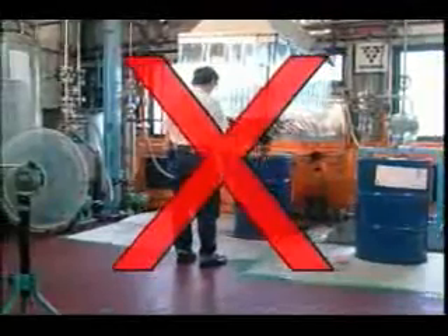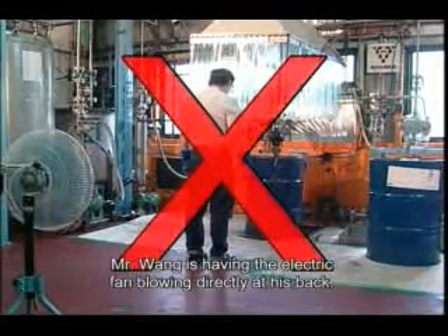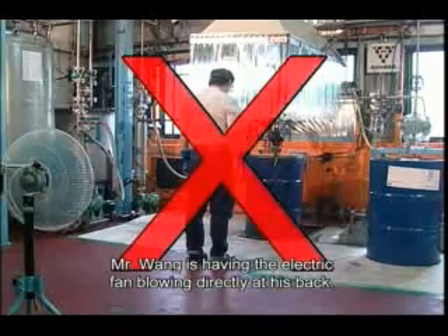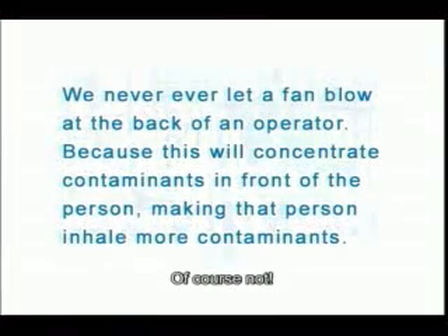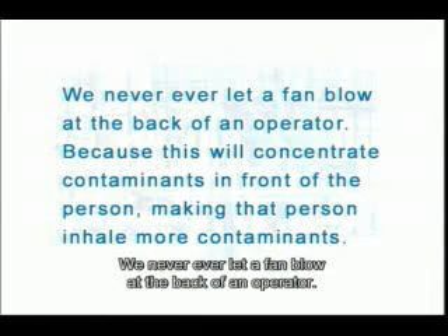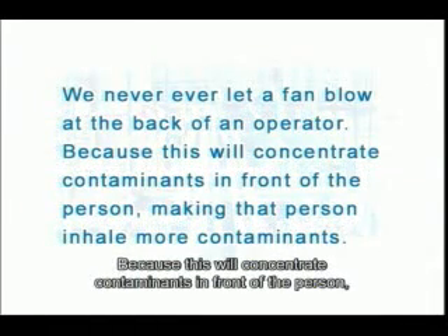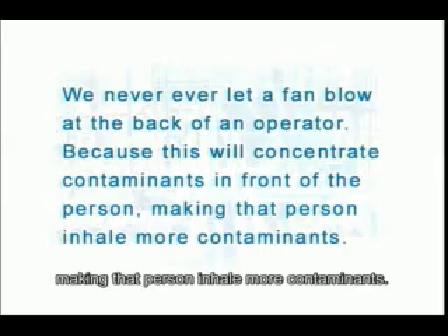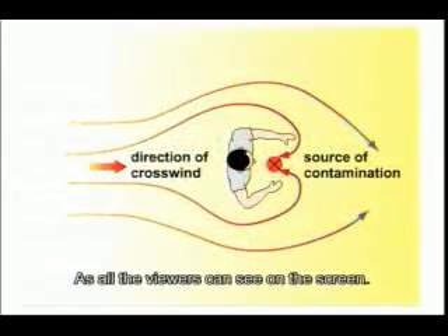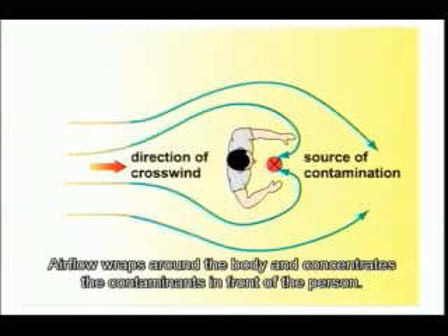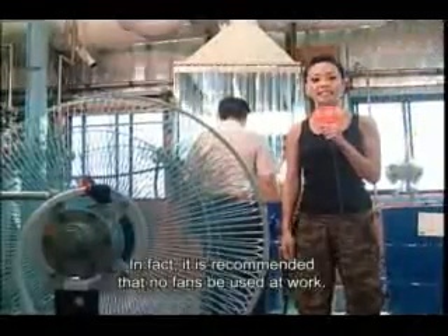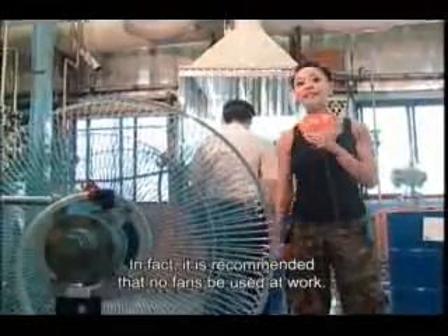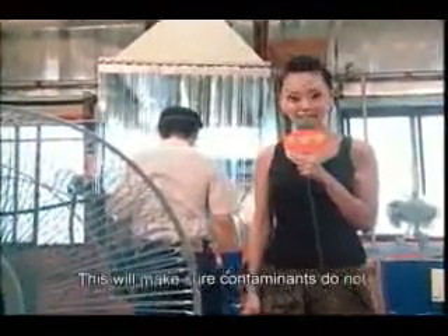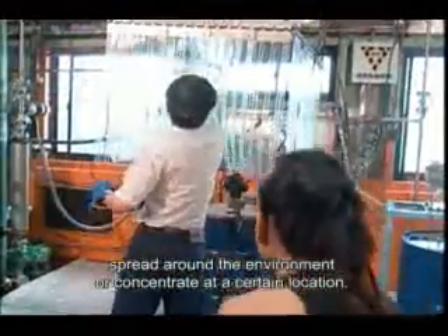Mr. Wang is having the electric fan blowing directly at his back. Is it correct? Of course not. We never ever let a fan blow at the back of an operator, because this will concentrate contaminants in front of the person, making them inhale more contaminants. As all the viewers can see on the screen, airflow wraps around the body and concentrates the contaminants in front of the person. In fact, it is recommended that no fans be used at work. This will make sure contaminants do not spread around the environment or concentrate at a certain location.